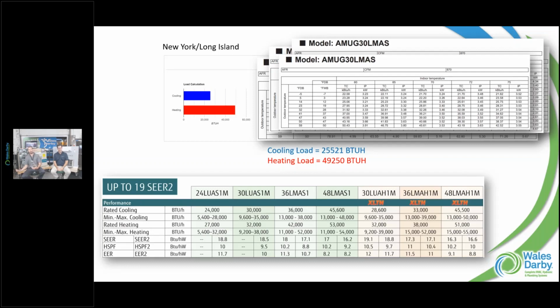So this is where we'll go back and look at those higher temperatures. On a 41-degree day, I'm giving you about 36,000 BTUs. 36.21 on 41? Yeah. Looking at those numbers, there's no right or wrong answer there, I can take any one of those numbers. I'm probably pretty close as far as a 41-degree day. I don't need 49,000 BTUs; I need that on a 14, 15-degree day. On a 41 or 47-degree day, I might only need 34,000 to 35,000 BTUs to heat that home. And this is where we'll match to there.